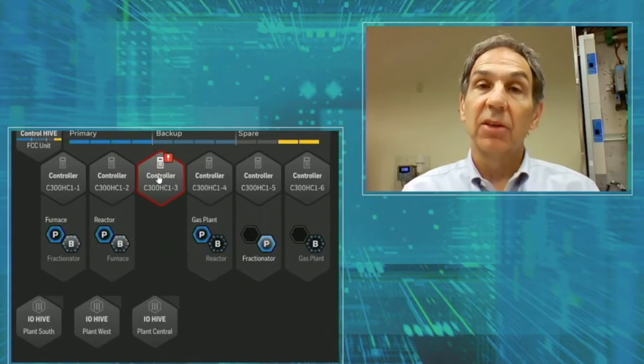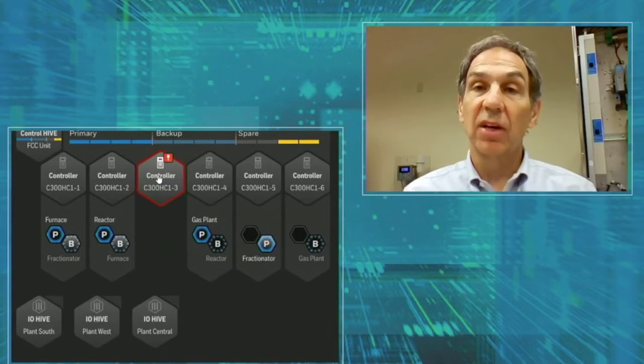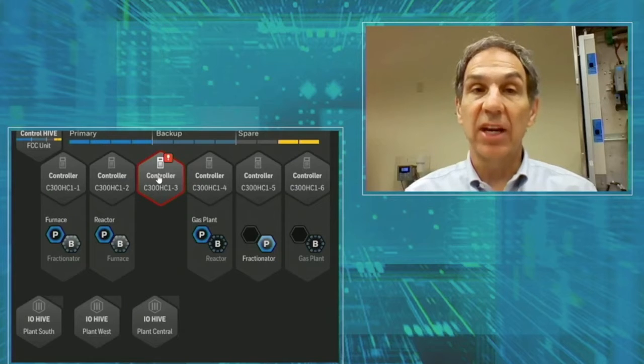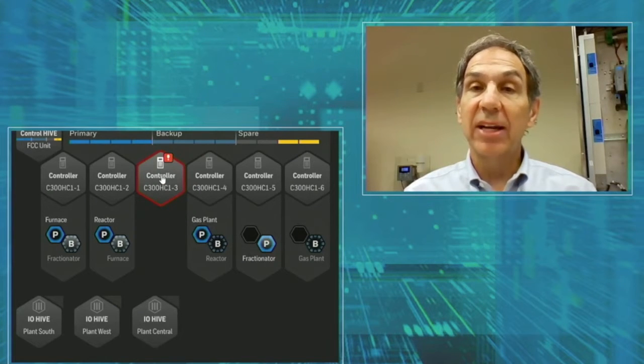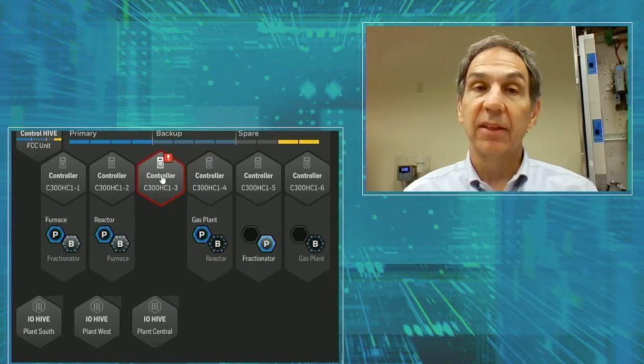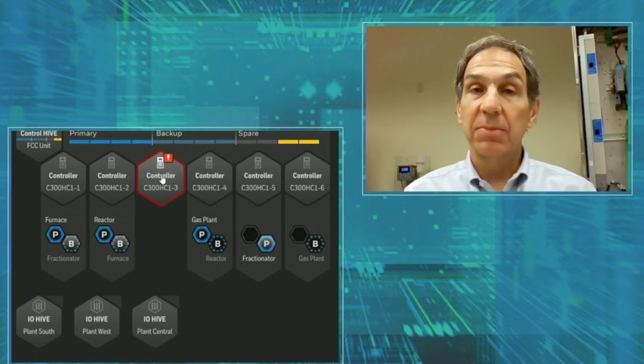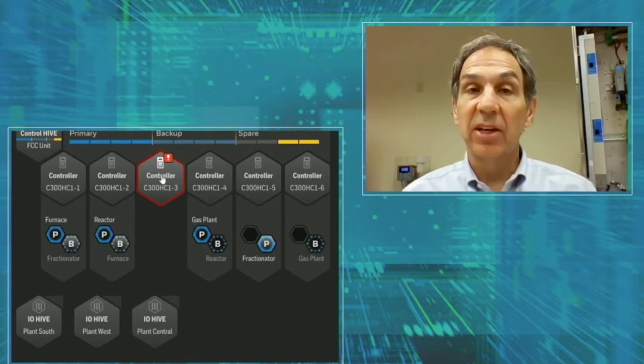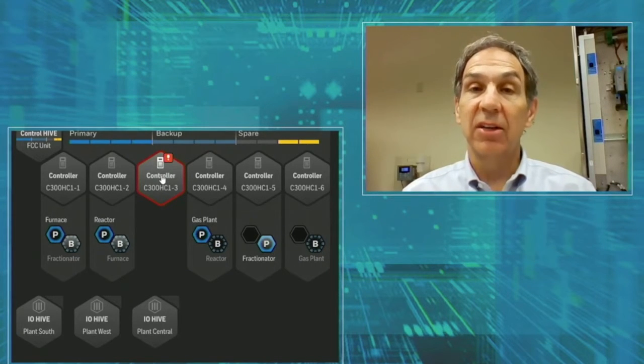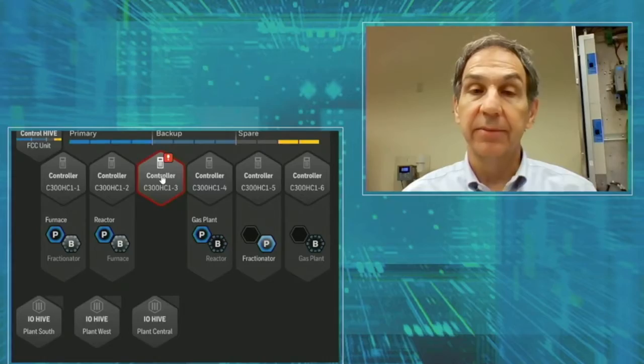A mouse-over on the failed controller highlights what has changed: the primary Fractionator failed over to controller 5, the Furnace backup moved to controller 2, and the new Fractionator backup initiated on controller 1.